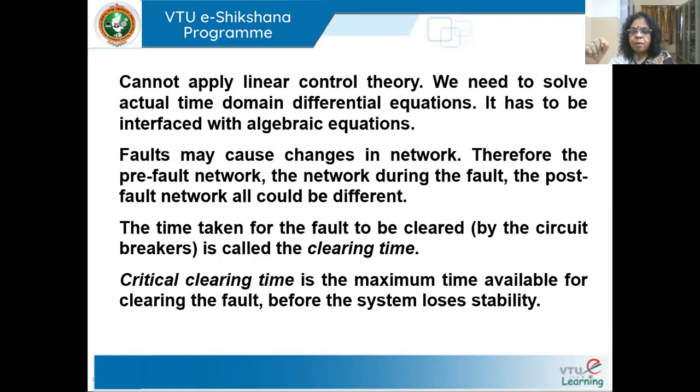So you can say the critical clearing time for the system for a three-phase short circuit at bus number 5 is 250 milliseconds. Clear? And likewise, you can say the critical clearing time for a three-phase fault at bus number 10 is 100 milliseconds. So you can quote like that.